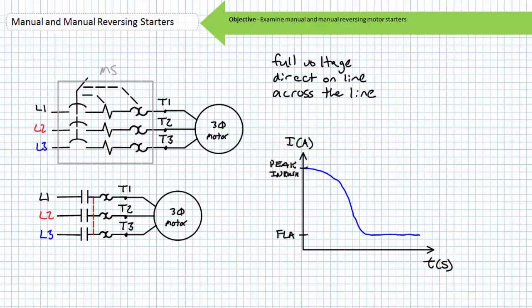If however a motor is subjected to a high inertial load, an industrial three-phase AC system lost a phase, or the rotor somehow locked due to a misaligned shaft or bad bearings, the inrush condition could continue. It is for this reason overloads are included in a motor starter. The overload elements in series with the contactor and the motor are intended to detect the sustained current and signal the primary contacts to open.